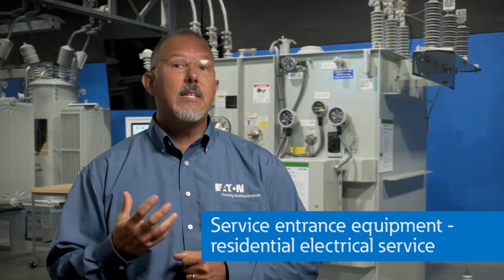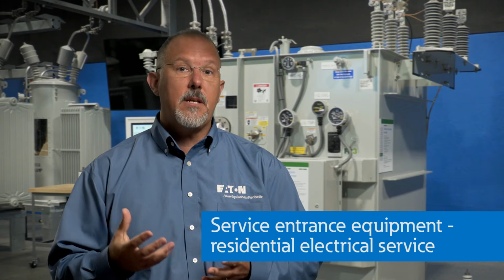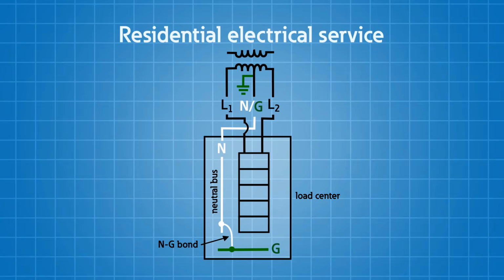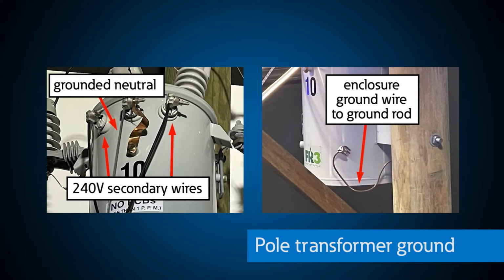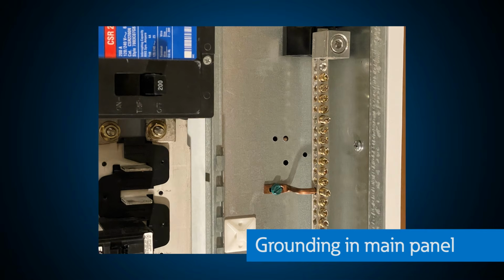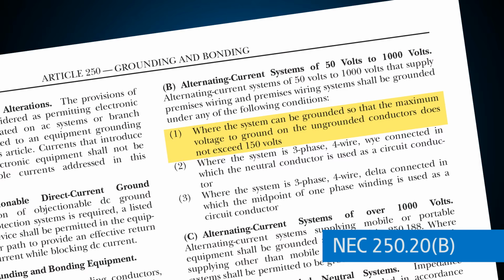Let's show you how a residential service and a load center are typically grounded and bonded. A residential system is a solidly grounded system with two hots and a grounded neutral conductor, which is a single wire. This allows the utility to ground the transformer and you to ground your main load center without dividing the current going back to the source because there's only one wire. NEC section 250.20(B) tells us that all premises wiring systems shall be grounded when the voltage to ground on the ungrounded conductors doesn't exceed 150 volts.